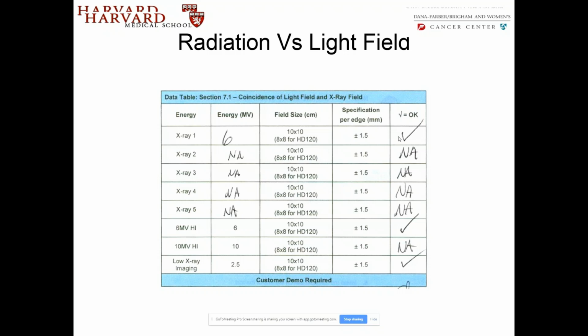So we have 3 energies on that machine. One is 6, the other is 6 FFF, which is flattening filter free. And then there is the imaging energy of 2.5. So for each one of them, we go through this process. If it is within the tolerance specified by the manufacturer, I will go out and accept that part of it.